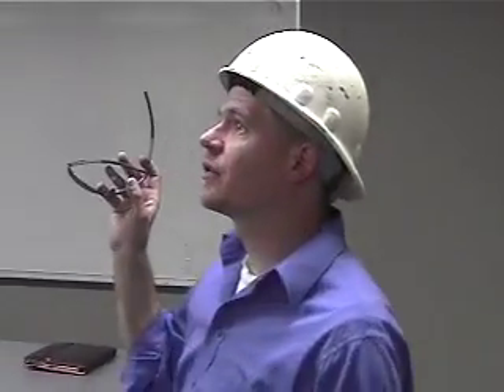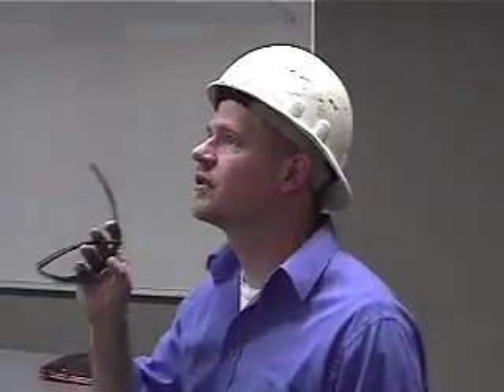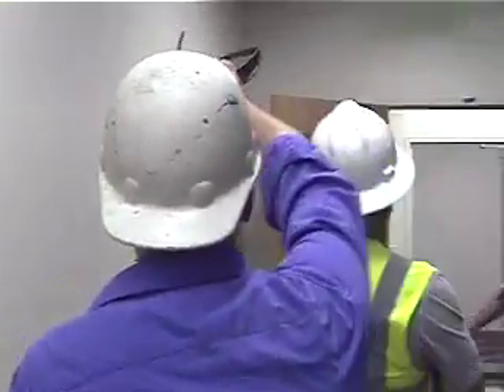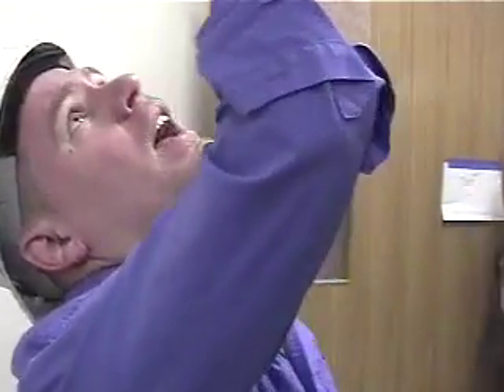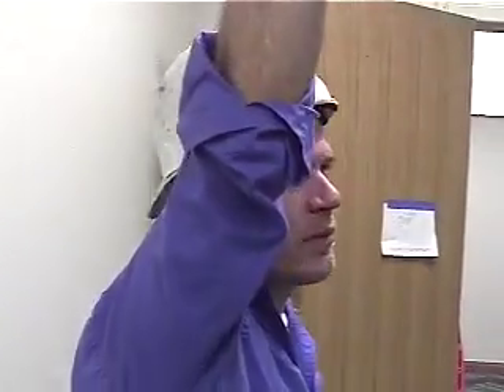See if we can find the supply in this room. Where's the supply register? Over here? Okay. Here's a double supply valve, and you can see that this one has your insulation on it, like I was saying. So this is bringing your air in, and you've got a heating coil that's driven by that supply valve as well. That's actually from an analog output from the valve, so it is a 0 to 10 signal to that heating actuator to be able to maintain your space temperature in the room. It's driven off the thermostat over here.